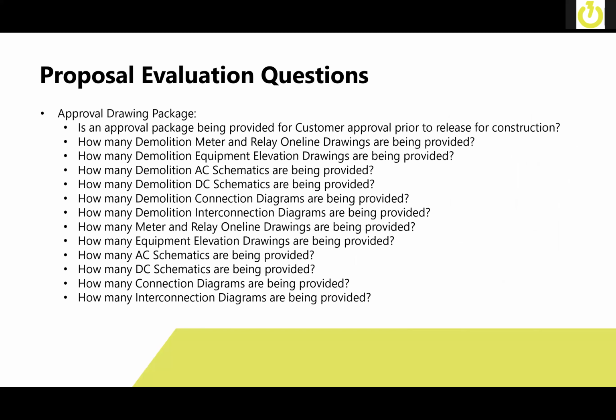For instance, in an approval package being provided for the customer approval, do you need to provide demolition meter and relay drawings? Do you need to provide demolition equipment elevation drawings, demolition AC schematics, DC schematics, demolition connection diagrams, interconnection diagrams? And maybe you need those in your application, maybe you don't. It's something that's recommended, just so you can always go back and see exactly what's being taken out in case something doesn't work properly whenever you get it all installed.